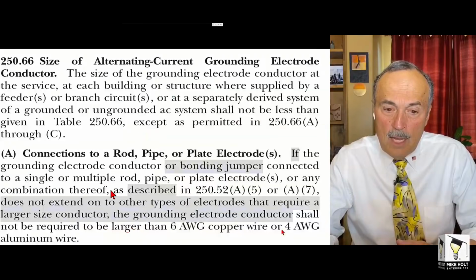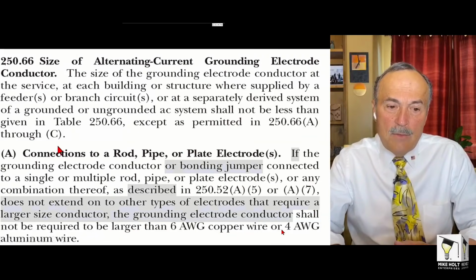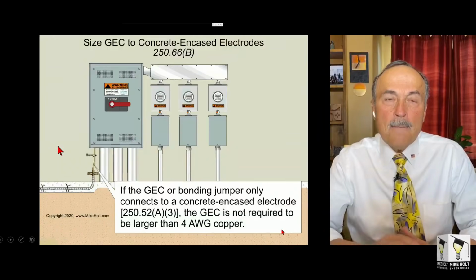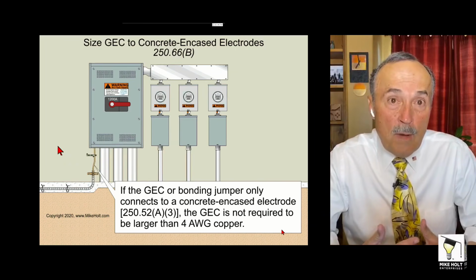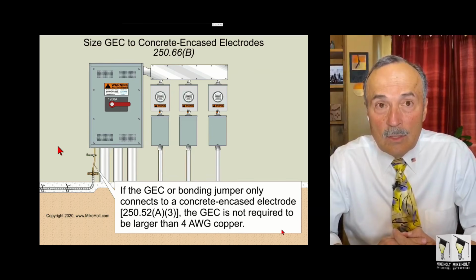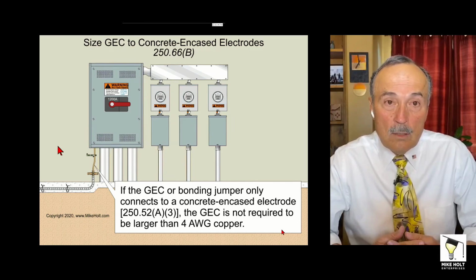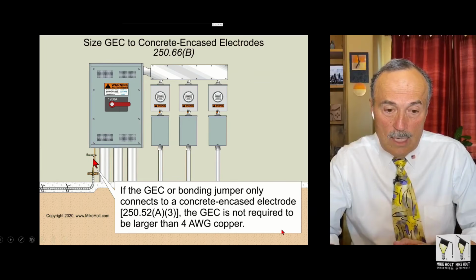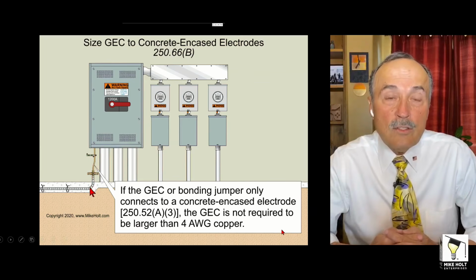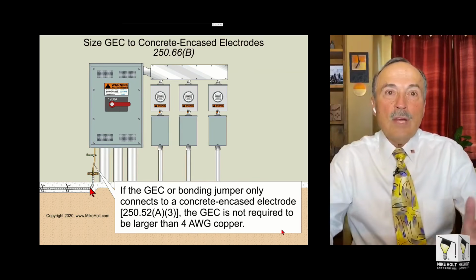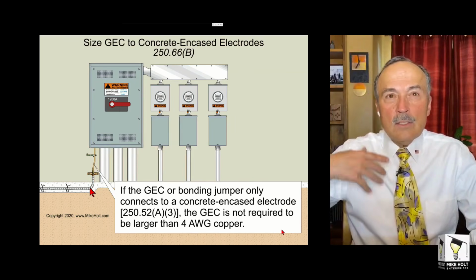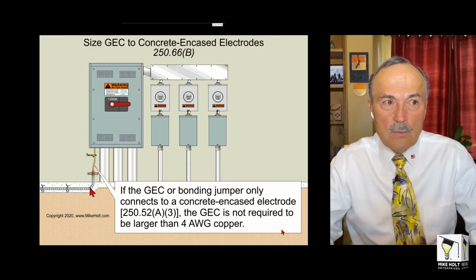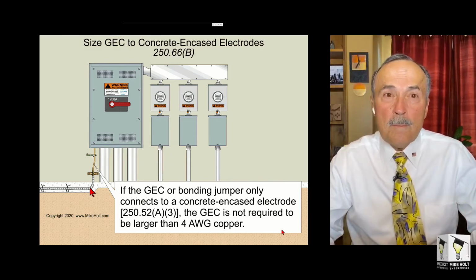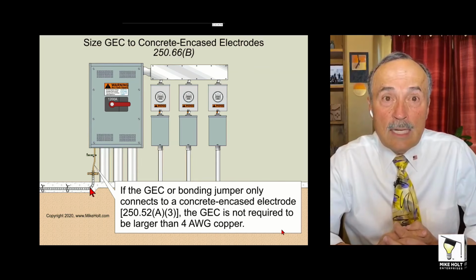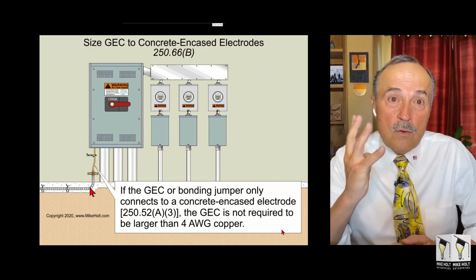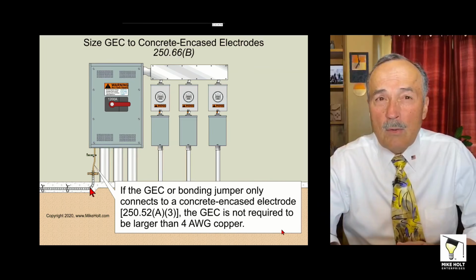Then it goes on, if you read, it's except as A through C, let's go to B. B has to do with the most common electrode that we're probably using today, which is a concrete encased electrode, rebar. Well, then the largest wire for a concrete encased electrode is going to be 4 gauge. Because the rebar, again, we're not trying to clear a fault. The electrons aren't going anywhere. This is system grounding and equipment grounding, not clearing a fault. It's 250.4(A)(1) and 250.4(A)(2). So what size wire would I run to a concrete encased electrode regardless of the size of the service? 4 gauge copper. Wouldn't put it any bigger, it's not required.